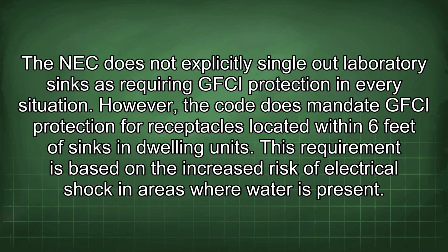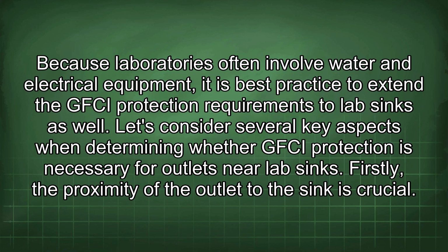The NEC does not explicitly single out laboratory sinks as requiring GFCI protection in every situation. However, the code does mandate GFCI protection for receptacles located within 6 feet of sinks in dwelling units. This requirement is based on the increased risk of electrical shock in areas where water is present. Because laboratories often involve water and electrical equipment, it is best practice to extend the GFCI protection requirements to lab sinks as well. Let's consider several key aspects when determining whether GFCI protection is necessary for outlets near lab sinks.